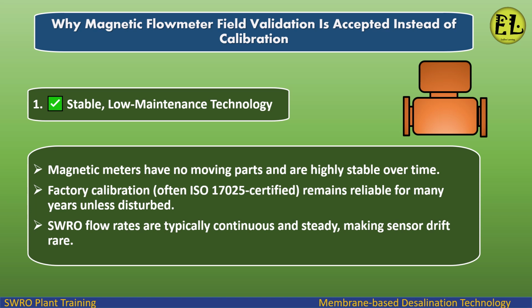Stable, low-maintenance technology. Magnetic meters have no moving parts and are highly stable over time. Factory calibration, often ISO 17025 certified, remains reliable for many years unless disturbed. SWRO flow rates are typically continuous and steady, making sensor drift rare.